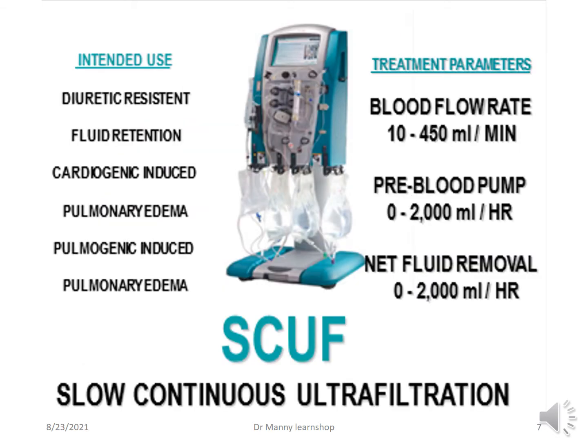So let's review SCUF from a Prismaflex perspective. And again, this is just an overview. So SCUF is slow continuous ultrafiltration, and it's for all the intended uses we mentioned previously: diuretic resistant fluid retention, pulmonary edema, which can be cardiogenic or pulmonic. Treatment parameters: the blood flow rate can go from as low as 10 to 450 mL per minute. It can have a pre-blood pump solution from 0 to 2000 mL per hour, and a net fluid removal from 0 to 2000 mL per hour.